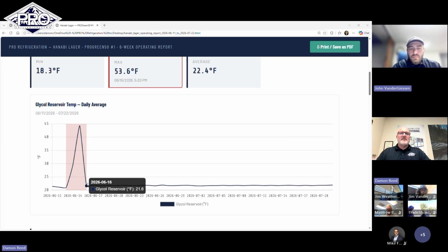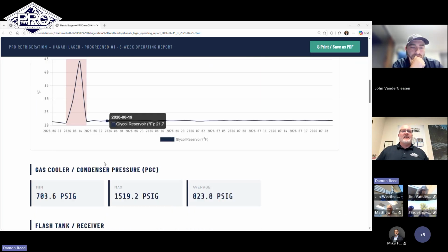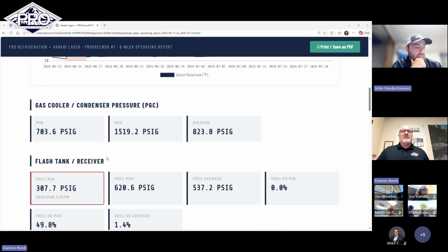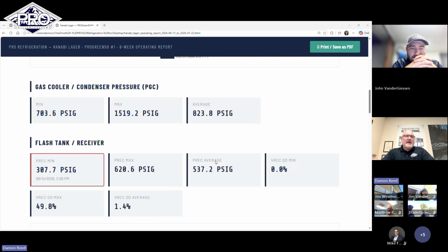Nice. And this will support, as I go through the rest of our operating data here, because we did pick that up on the flash tank receiver pressure as well, where it dropped down to 300 psi, and I'll talk more about that. Gas cooler pressure, everything looked good. On the low end we saw 700 psi. On the max we got up to 1500, and we averaged 825. So those are good, solid ranges I'd expect to see.